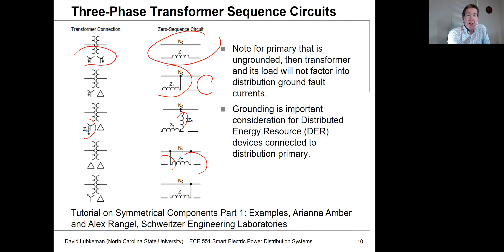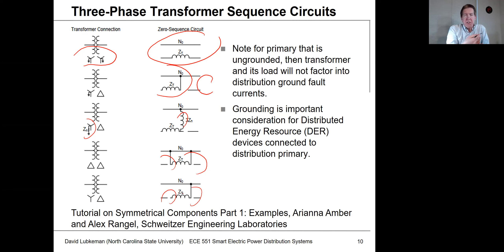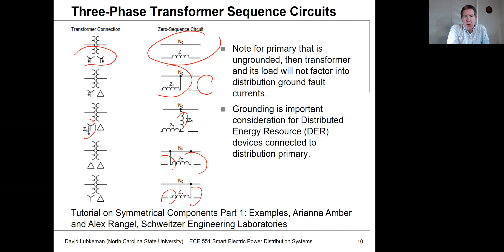With delta-delta, you get circulating currents but the path is open on both sides. With ungrounded Y-delta, you get an open circuit. All of this comes down to what you want to happen with the zero-sequence path when you have ground faults. I'll go ahead and post a couple tutorial papers by Schweitzer Engineering Labs on symmetrical components as a reference.